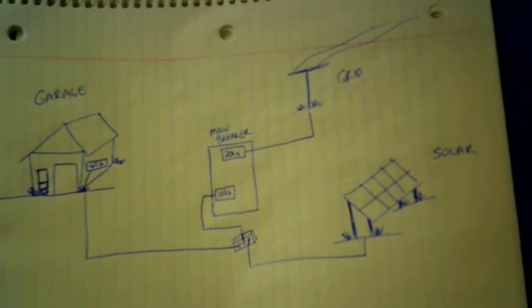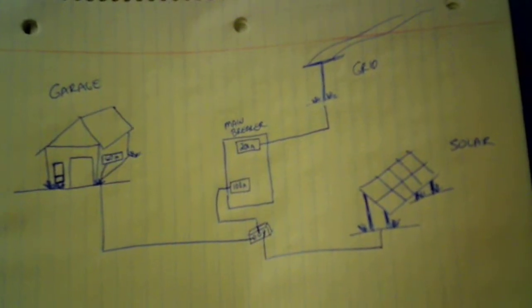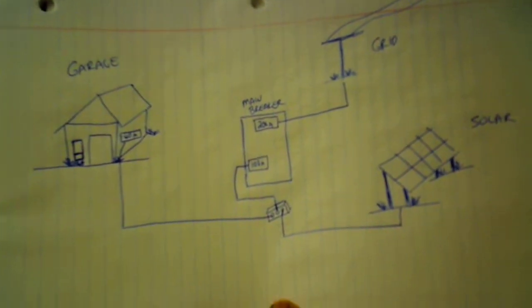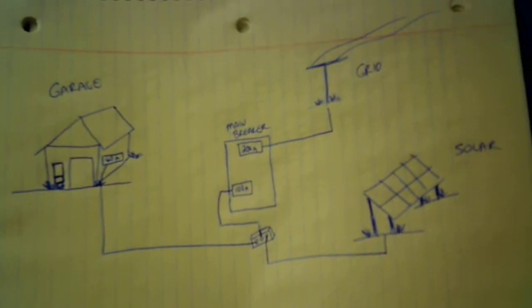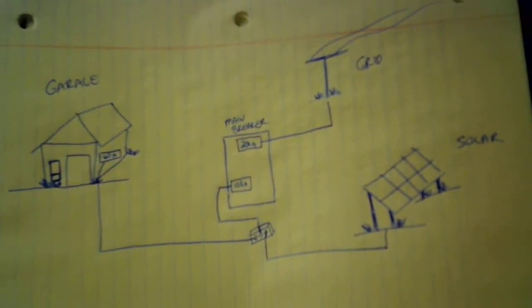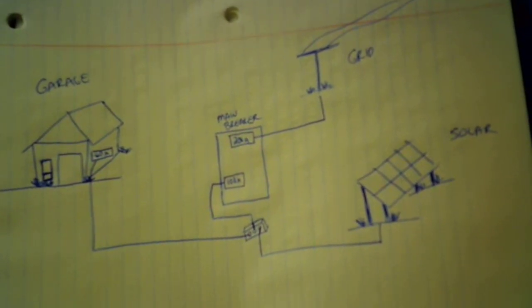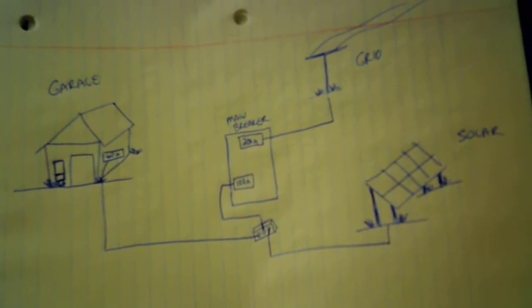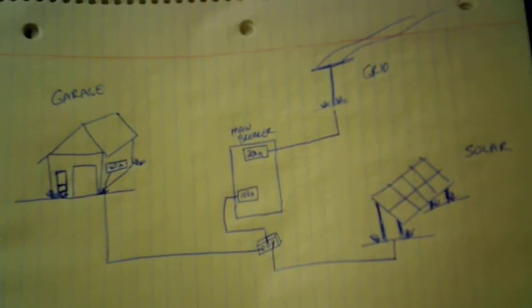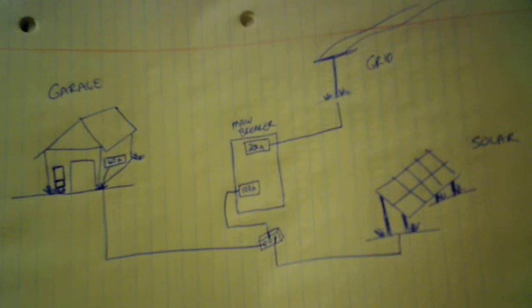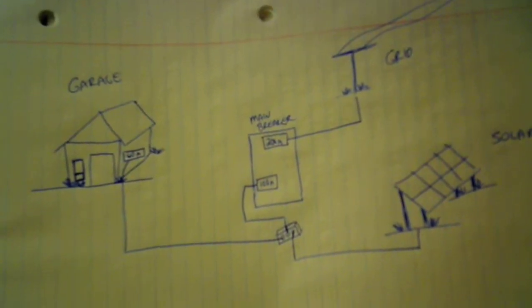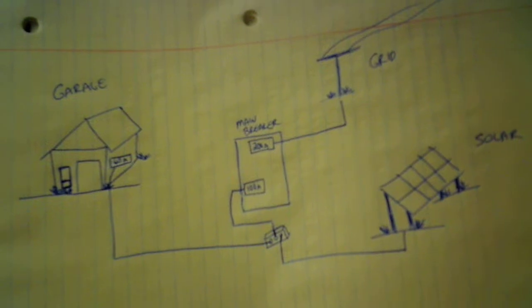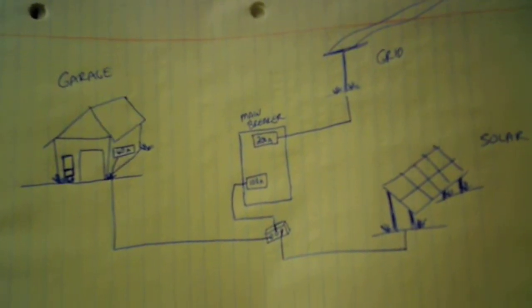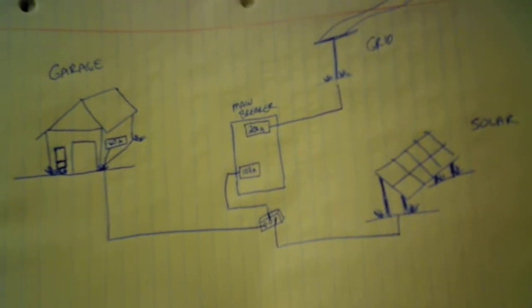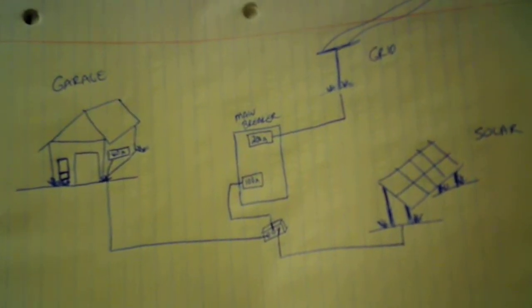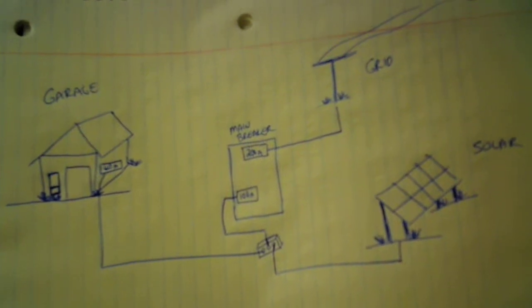If it's been cloudy for a few days, or I've charged all my electric cars and my battery bank is low, I can switch it so that the garage only is off-grid. The way that works is I'd have the 200 amp service on, the 100 amp sub-panel breaker off, and power would feed from the solar panels through the junction box into the garage and charge my batteries. If I wanted to be fully off-grid, which I probably have to do in winter sometimes, I'd turn off the 60 amp breaker in the garage that the inverter goes through.